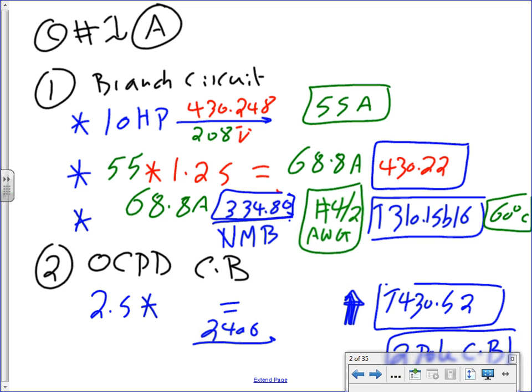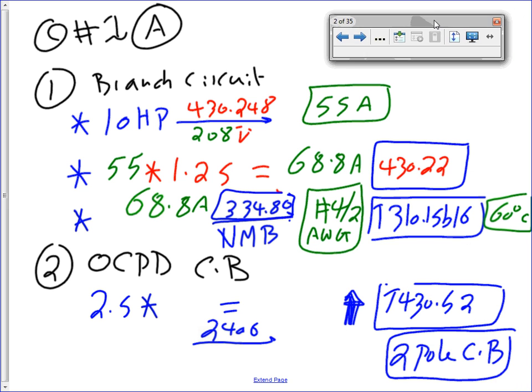When you go to this table, B.310.15(B)(16), because it's NM-B, 334.80 tells you that for NM-B you always have to use the 60-degree column when you size, because it's not as robust a cable as MC cable. So you limit the amps to the 60-degree column. In residential, most of what we do is practically type 3, 4, and 5, and mostly type 5 buildings, which are wood buildings. Any comments, guys, about this one? Any questions? Straightforward, right? We've done that before.